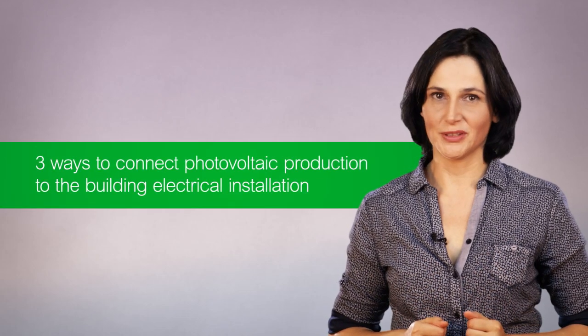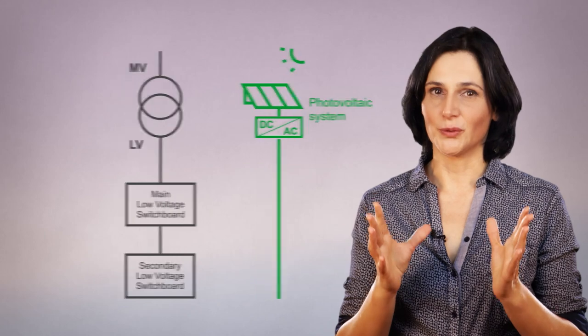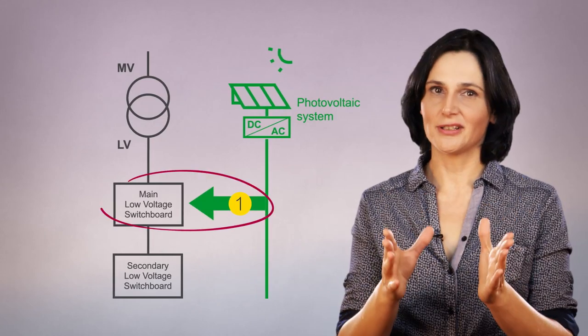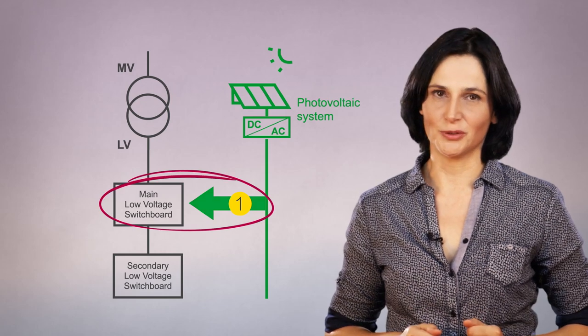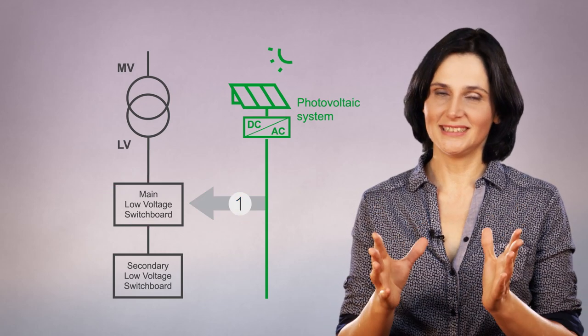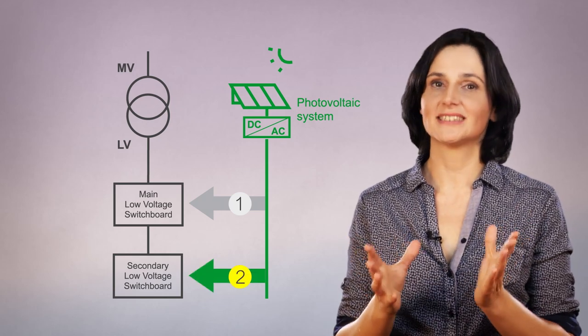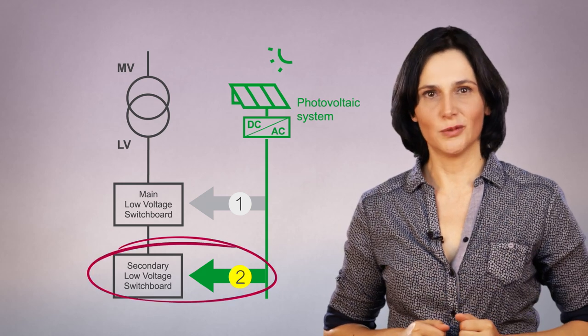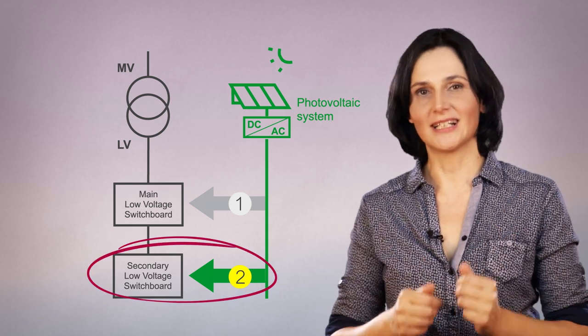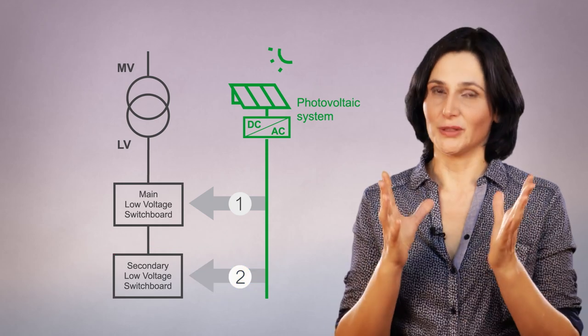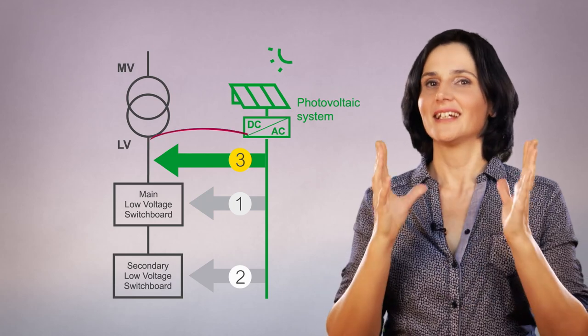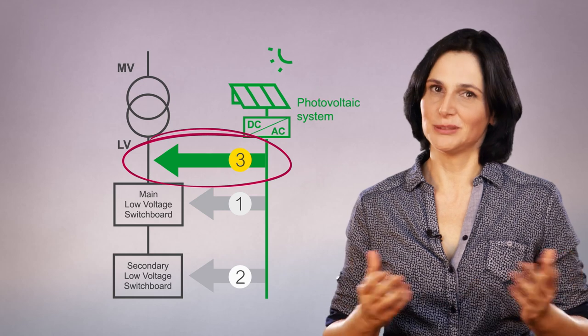To summarize, we have seen three ways to connect photovoltaic production for self-consumption. For new sites, where the photovoltaic production is part of the initial design: direct connection to the main low voltage switchboard. For existing buildings, especially multi-floor buildings or buildings with small scale production: connection to a secondary low voltage switchboard, usually the closest one. For existing buildings with photovoltaic production exceeding the building's consumption: connection upstream to the main low voltage switchboard is preferred.